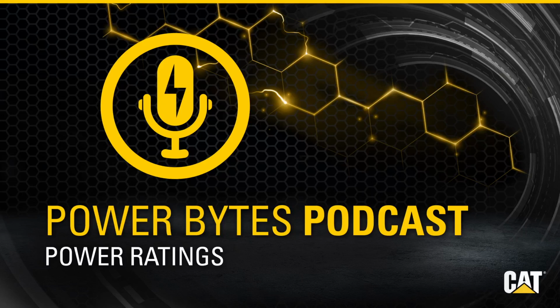So again, we can now take that same generator set and rate it for a continuous application, where it's able to run at 100% load factor for unlimited hours. So in order to reach those operational characteristics, we need to again reduce the rating of the generator. So that generator would be rated for 2,000 kVA. So you can see if we take the same product and we're running it for a short period of time, we're able to run it at a higher power. So we're at 2,500 kVA standby. But if we're going to run it at its maximum capability, that would be a lower power set, around 2,000 kVA.